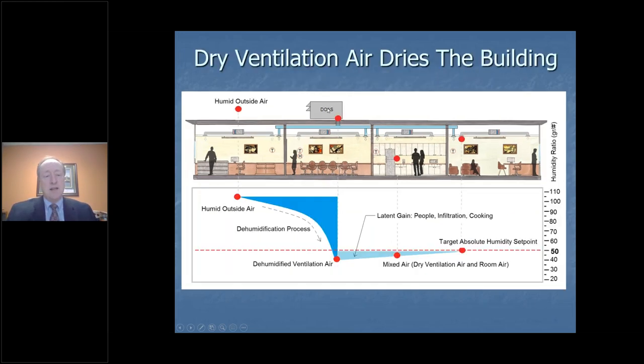But you ask me, well, how dry do I need to make the air coming out of this dedicated outdoor air system? Well, you go back to the formula that I was showing you earlier for the latent gain, and that's equal to, at least in the IP units, 0.68 times the difference in grains times the cubic feet of air going through this particular unit. So if I know the space condition that I want to maintain for the moisture is along this particular humidity ratio, then I know that I've got to deliver the air a little bit drier than that to start with, so that it can pick up the latent gain that I'm going to find in the space due to the people and the coffee pot and fountain that may be in the lobby, anything else that may be the latent gain.